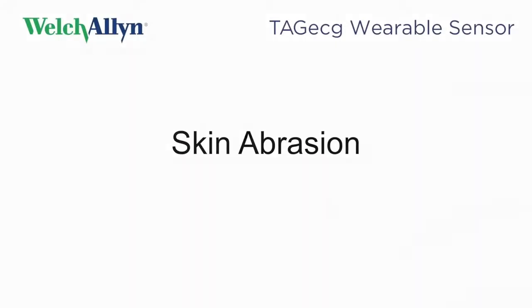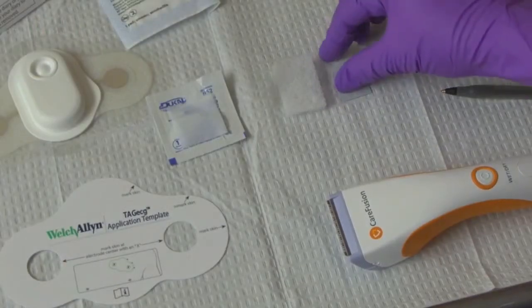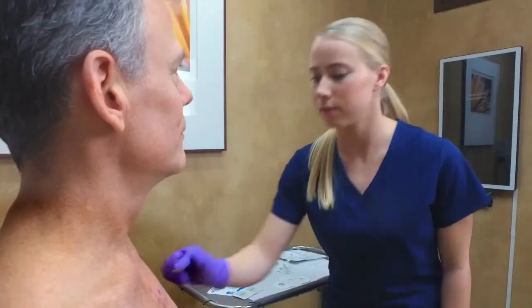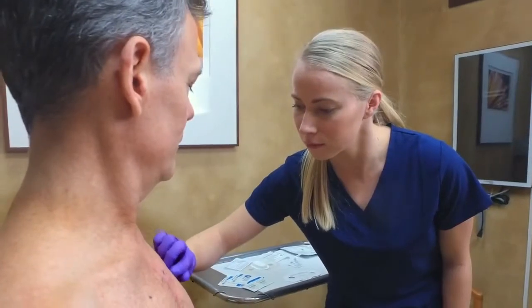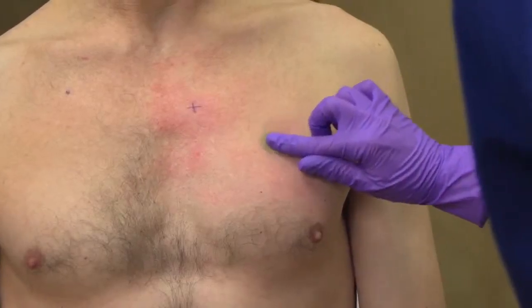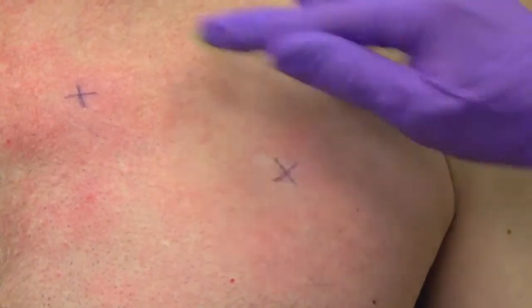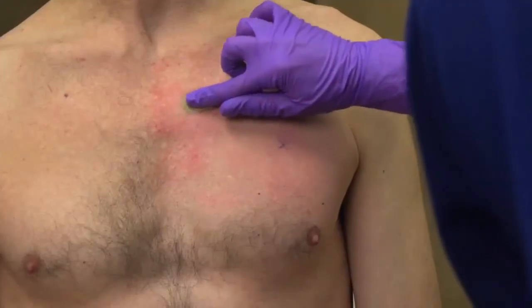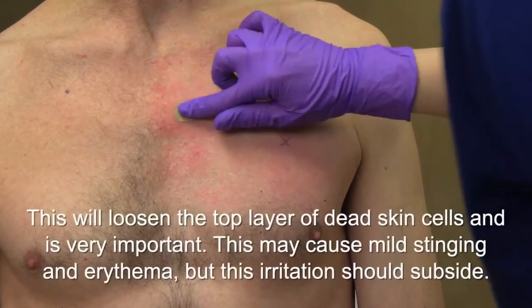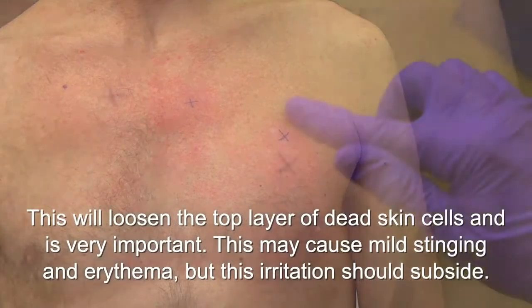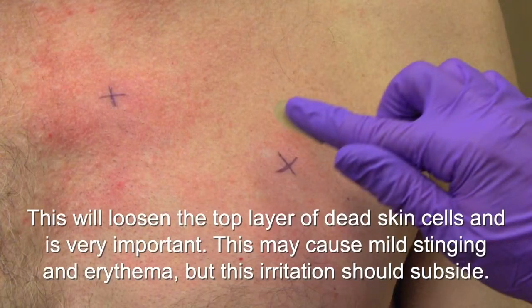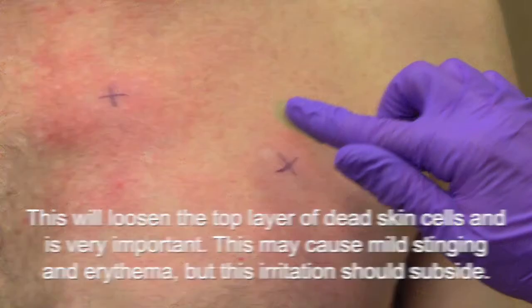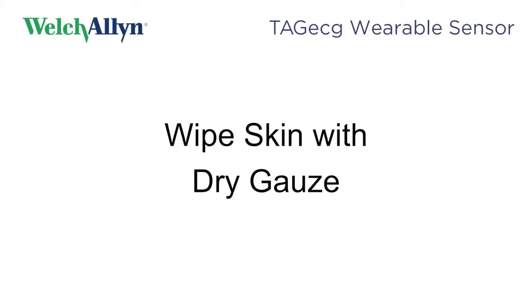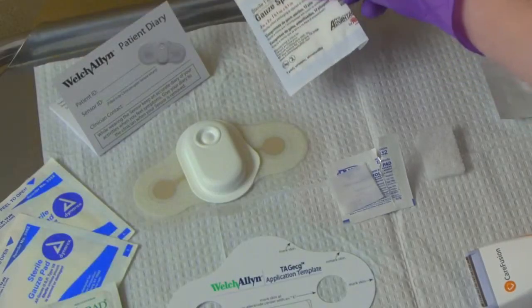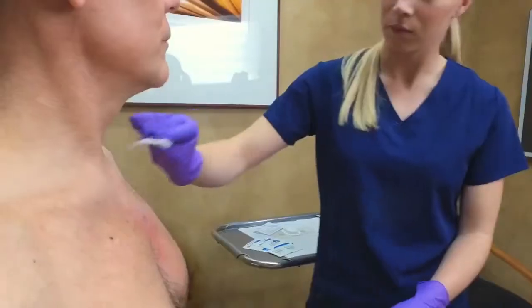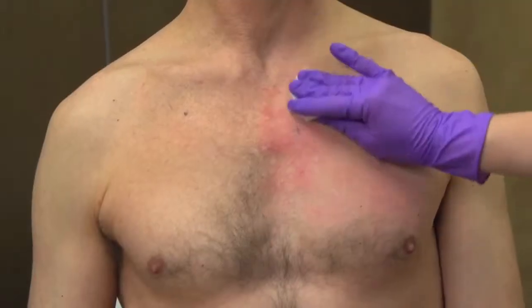Abrade the skin. Select one of the 2 provided skin abrasion pads in the patient's supplies. Our model will demonstrate how to prepare the patient's skin using the sandpaper-type skin abrasion pad. Rub gently only over each of the 2 X's marked on the patient's skin, using a circular motion, and abrade over each X only once. This will loosen the top layer of dead skin cells, and it is a very important step. This may cause mild stinging and erythema, but this irritation should subside. Wipe skin with dry gauze. Use the sterile dry gauze sponge, and more if needed, to wipe the entire sensor placement area to remove any remaining dead skin cells.